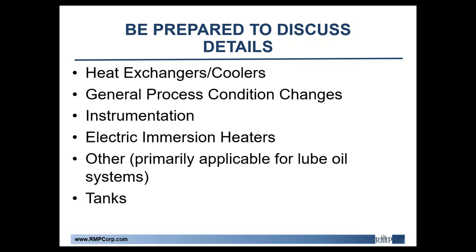You also want to be prepared to discuss details going in. For heat exchangers, know the impact of loss of heating, cooling, flow, or temperature on the system, including something like loss of cooler fans. For general process condition changes, know how the process will react to loss of flow, more flow, or high and low temperatures, and know the safety limits resulting in near or long-term damage. For instrumentation, know the protection system set points as well as alarm set points, locations, and alarm effects such as audible alerts or flashing lights. For tanks, know vent locations and affiliated hazards, tank maintenance and draining, secondary containment issues and draining requirements, and materials of construction.